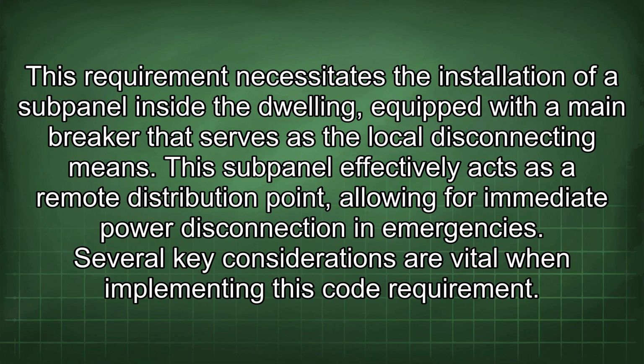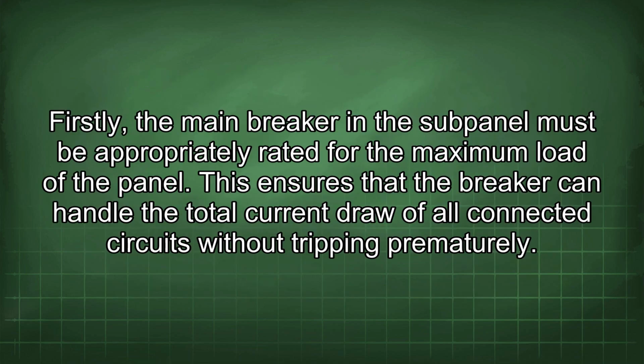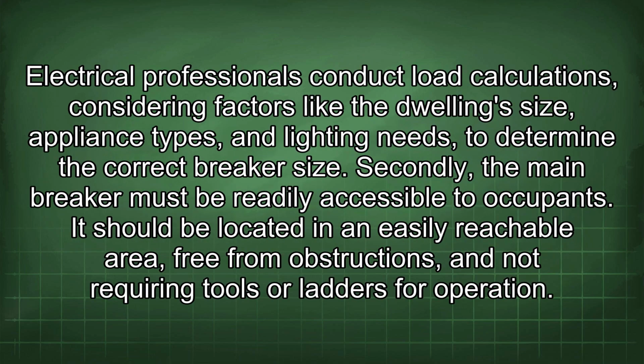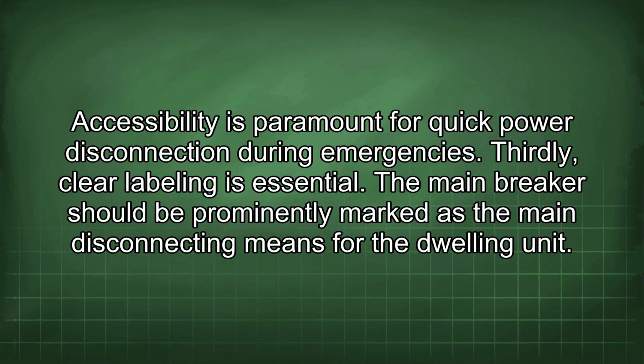Several key considerations are vital when implementing this code requirement. Firstly, the main breaker in the subpanel must be appropriately rated for the maximum load of the panel. This ensures that the breaker can handle the total current draw of all connected circuits without tripping prematurely. Electrical professionals conduct load calculations considering factors like the dwelling size, appliance types, and lighting needs to determine the correct breaker size. Secondly, the main breaker must be readily accessible to occupants. It should be located in an easily reachable area, free from obstructions, and not requiring tools or ladders for operation. Accessibility is paramount for quick power disconnection during emergencies.